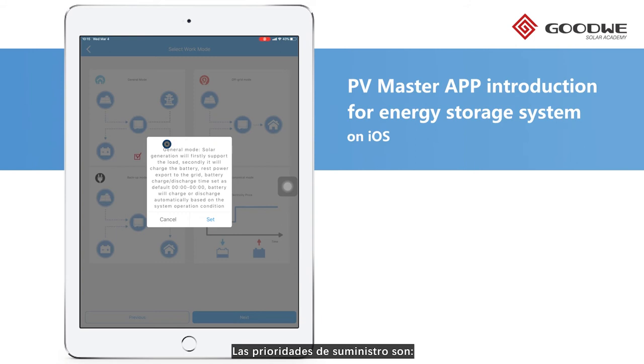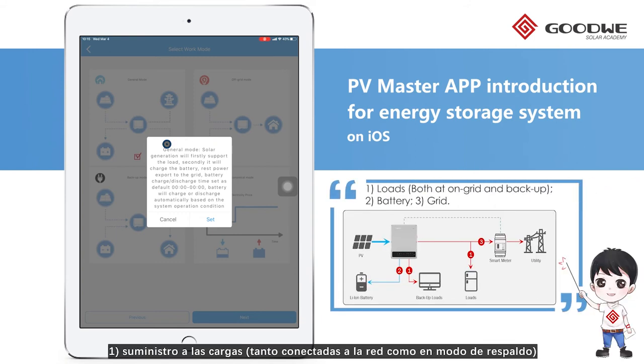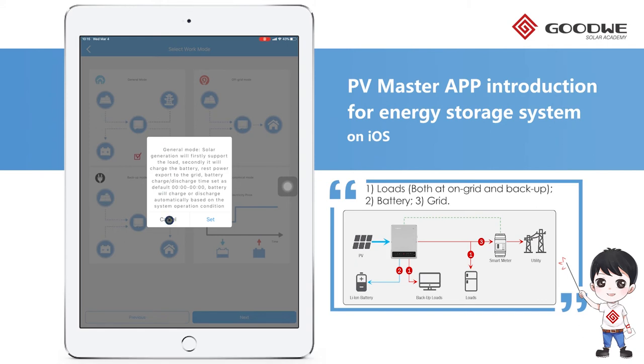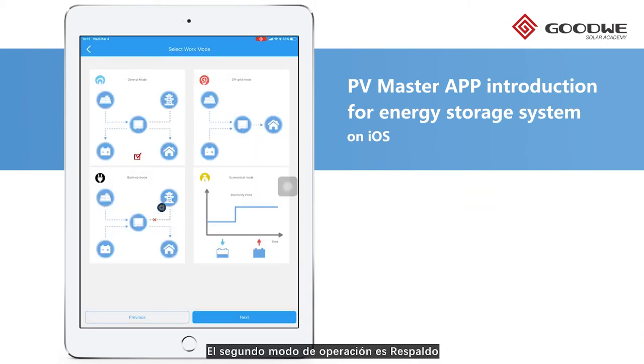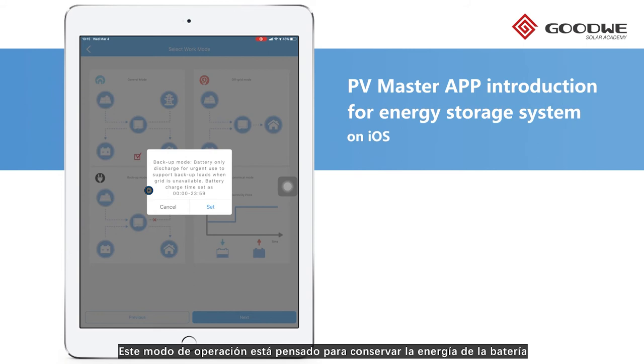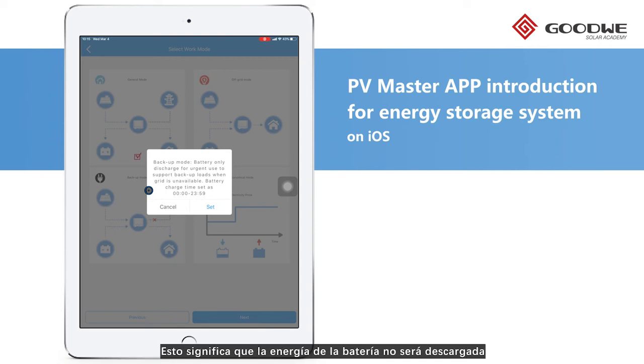The supply priority of PV power is loads, battery, and then grid. The second one is Backup Mode. This mode is to save battery power for emergency use during utility outage, which means the battery will not discharge when the grid is on.